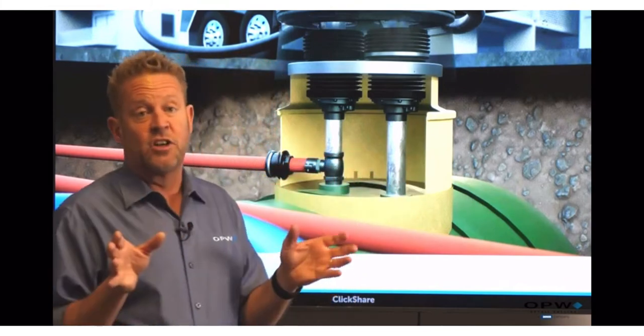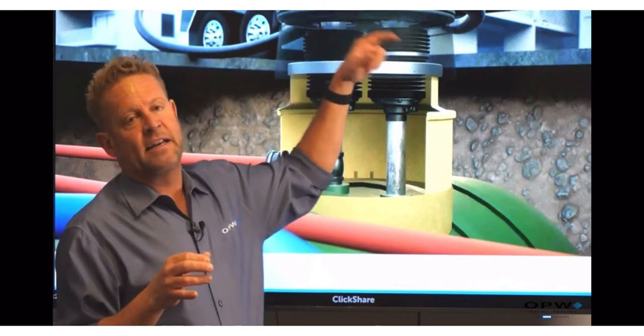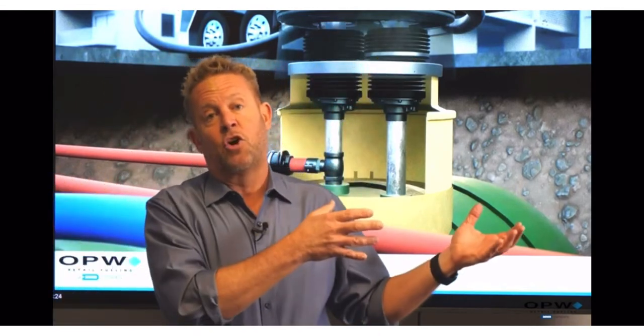What happens is as the fuel level rises, the vapor now, instead of going out our vent stack, comes up through our vapor recovery hose and actually goes back into the tank. So he's collecting those vapors back in the tank so everything kind of stays in balance. We prevent the vapors from getting in the air, and actually turns out to be a good thing because the vapors go back in the tanker truck.